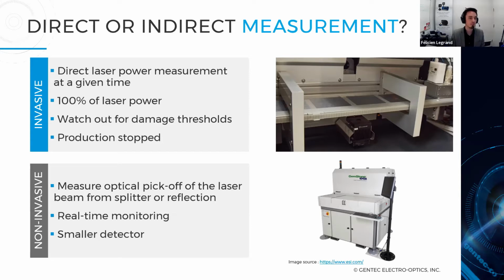A typical optical pick-off from a semi-transparent mirror could have a transmission between 4 to 10%, for example. So that will require a detector that's less capable than one taking 100% of the laser power. A smaller, lower-rated detector could be used for a non-invasive way to measure this, and that's more and more used, because you don't want to stop all your processes.